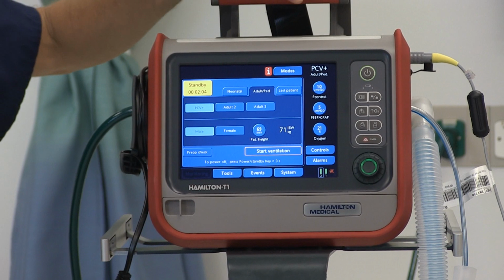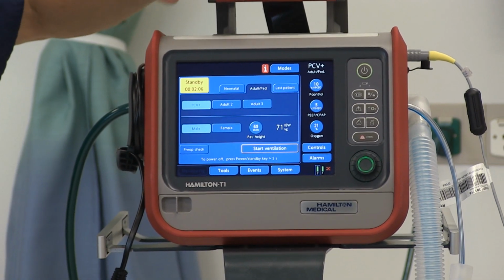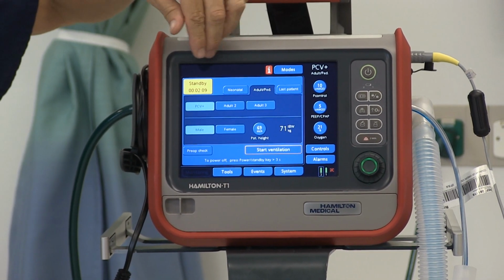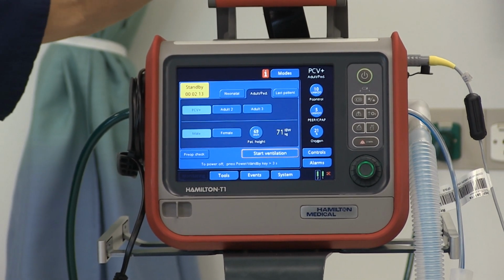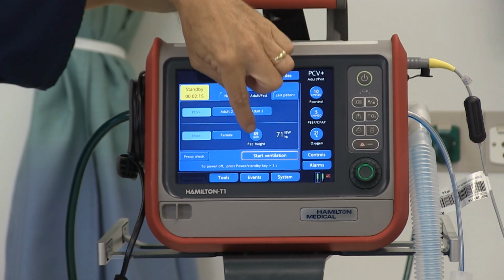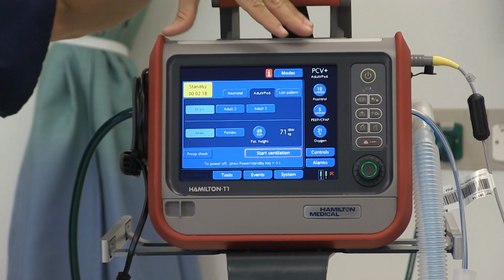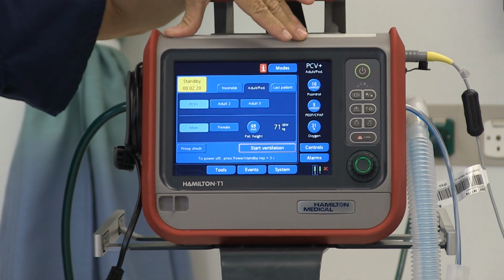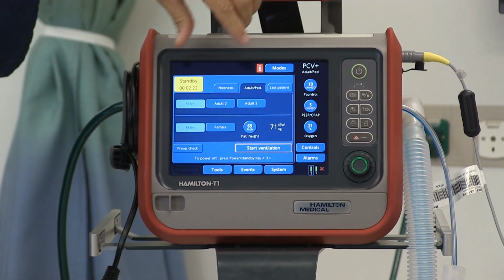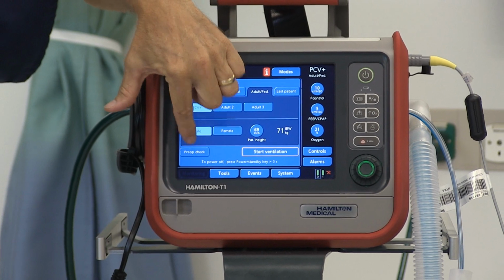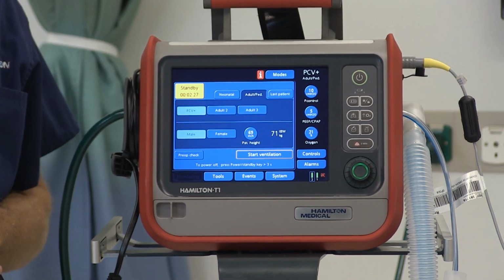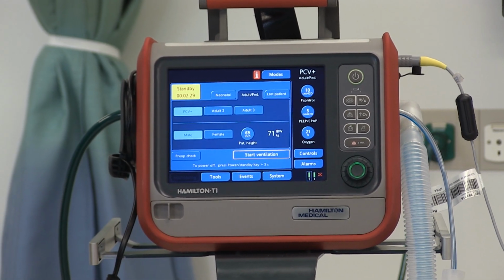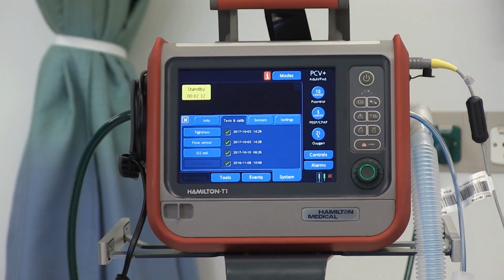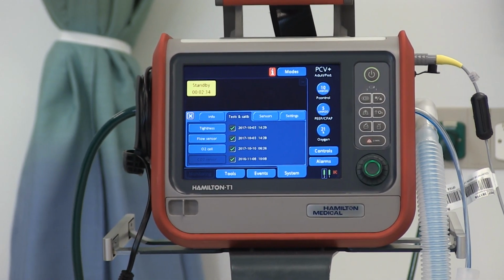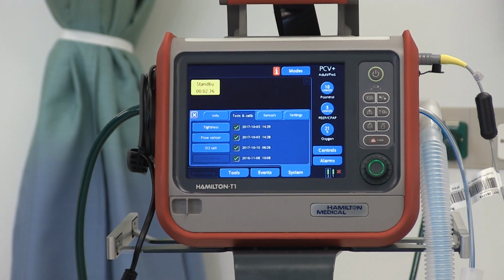There's 3 quick start settings. You can put in your own modes for a quick setup that is customizable. Below that, in this section, is patient information. So this is where you're going to put in the patient gender and the patient height, and the ventilator will automatically calculate the ideal body weight in kilograms. And just below that, there's a tab for the pre-op check. So let's go through the pre-op check. We have to calibrate the flow sensor and do a tightness check. So I touch that tab, it opens the systems window, and here are the pre-op check tests.